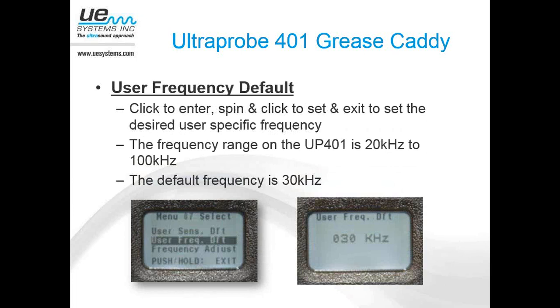So then the user frequency default. As I mentioned, on the Ultraprobe 401, we can adjust the frequency anywhere between 20 kilohertz and 100 kilohertz. But as you know, it's really about 4 different frequency settings that you need to remember for the different applications. The frequency setting that we recommend for bearings and mechanical inspection is going to be 30 kilohertz. Now that's not set in stone. We have some people that use different frequency settings for bearings, but as a company we recommend 30 kilohertz.